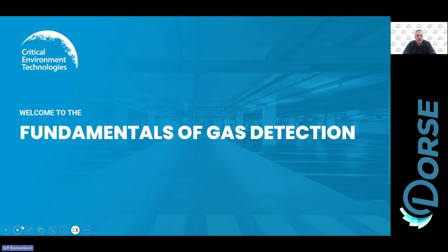So again, gas detection is a way to, yes, protect lives and protect property, but also protection of the environment, saving energy, saving money by only running those fans when required, when that ppm level or that lower explosive level gets up to a point where we need to clear out that air. Okay. There are a number of regulatory authorities that we in the gas detection industry focus on and look at when considering and designing our gas detection systems. And many of you, or most of you, if not all of you, will recognize at least one or two of these organizations on the screen here.